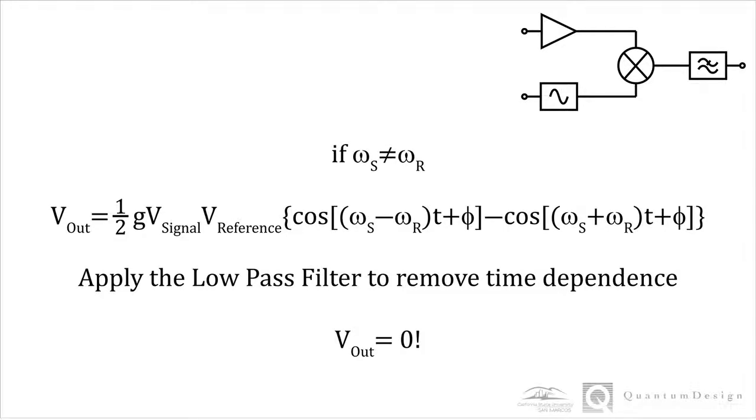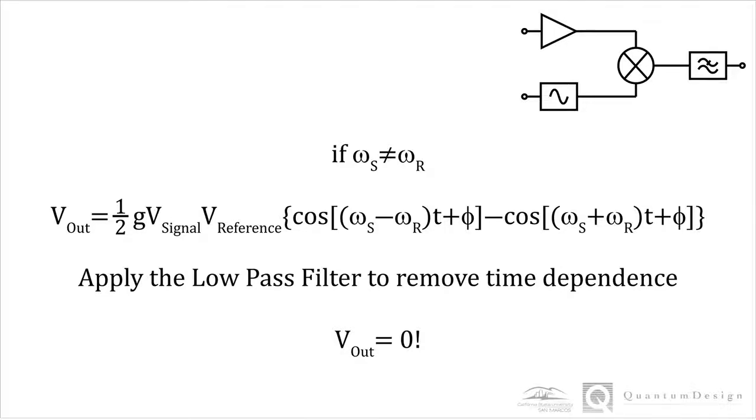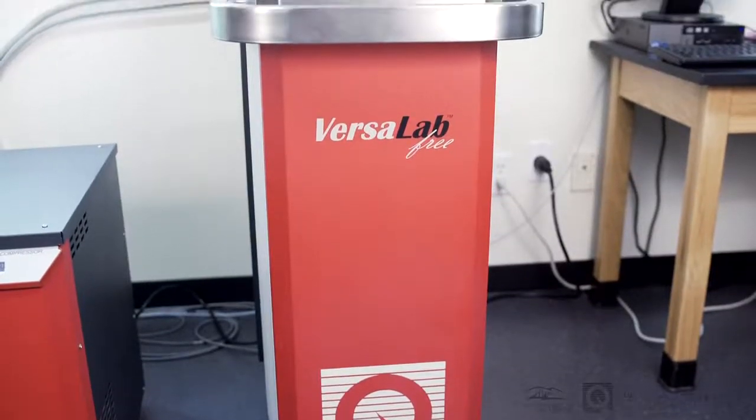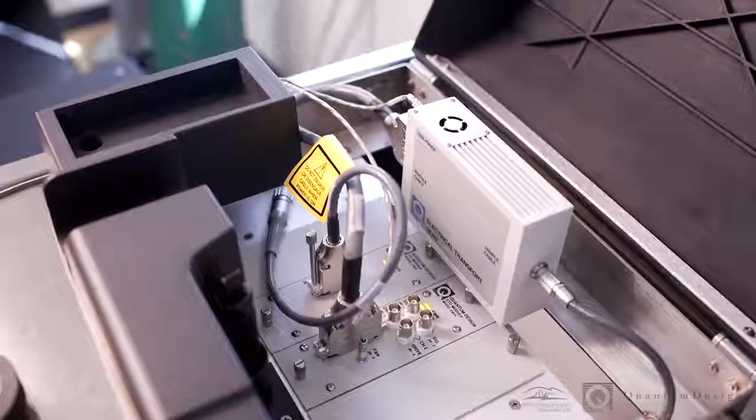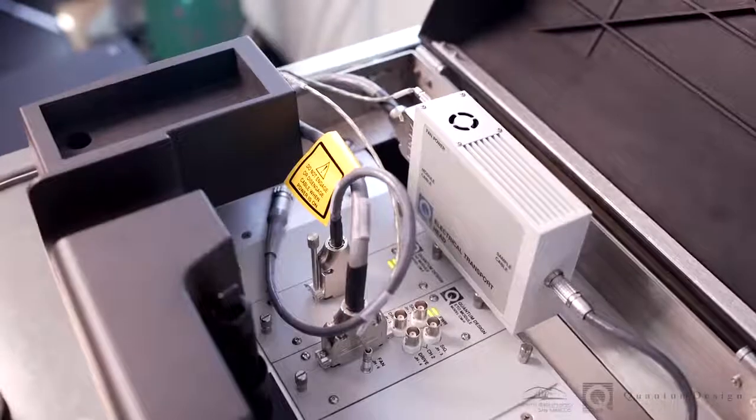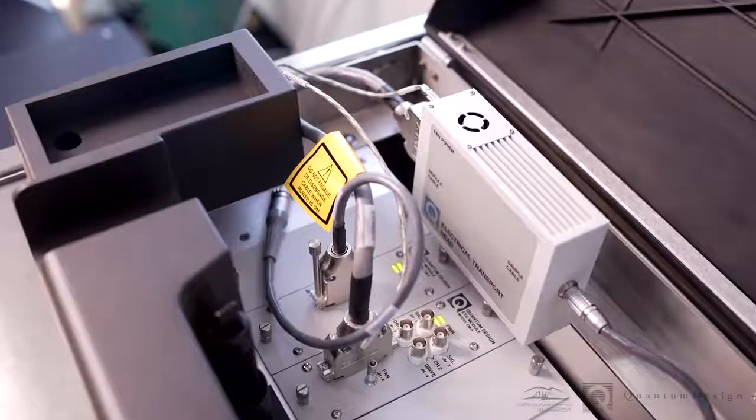We will soon demonstrate this using the electronic transport option, or ETO, module of the VersaLab. Before we perform a measurement with the ETO, we should note that our previous discussion has been about the analog lock-in technique. The VersaLab ETO performs measurements using a digital lock-in technique controlled by the module's digital signal processor, or DSP.